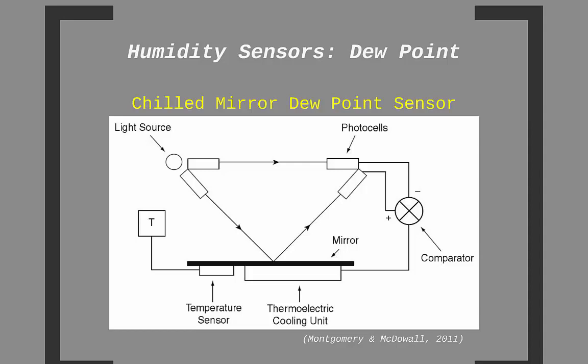A thermoelectric cooling unit will operate in a way to cool down the surface of a mirror. Once the temperature of the mirror reaches the dew point temperature of the air, moisture will begin to condense out of the air and onto the surface of the mirror. When this happens, the light that was being perfectly reflected from the light source and onto the lower photocell will become a bit scattered. The comparator will compare the amount of light coming directly from the light source and hitting the upper photocell to the amount of light being reflected into the lower photocell.